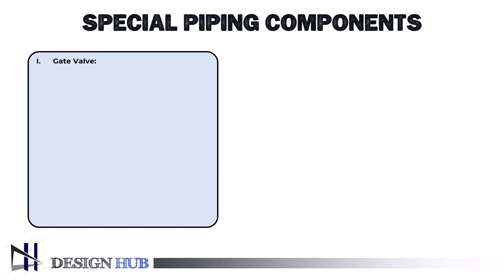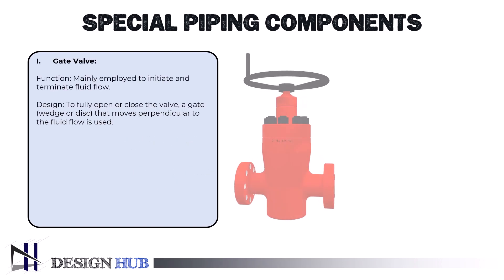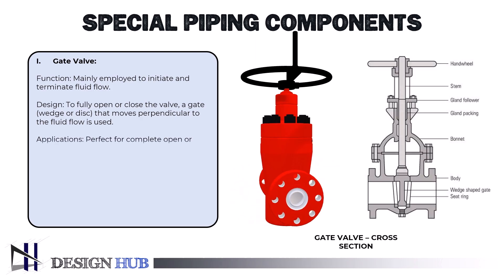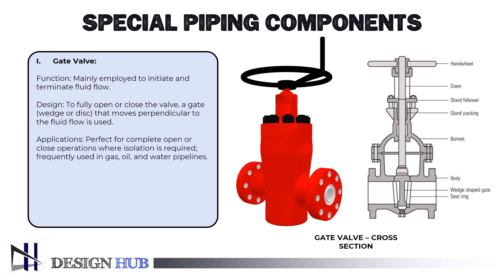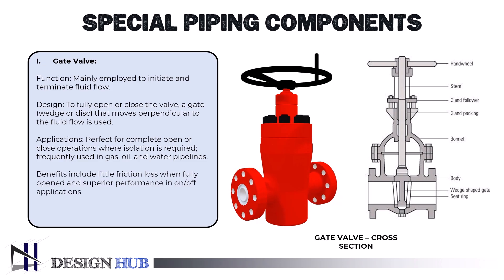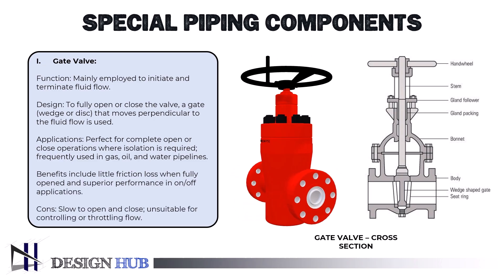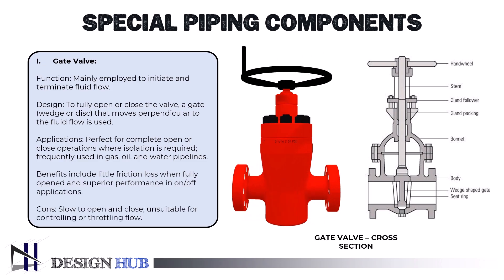Let's see what a gate valve is. Sometimes referred to as a sluice valve, it opens by raising a barrier, or gate, that blocks the fluid's flow. Gate valves need extremely little space along the pipe axis and rarely limit the flow of fluid when the gate is fully opened. Though they can be parallel, the gate faces are often wedge-shaped so that pressure can be applied to the sealing surface.